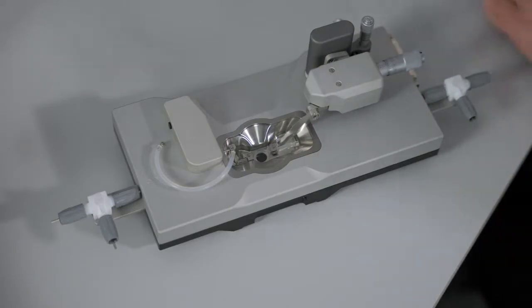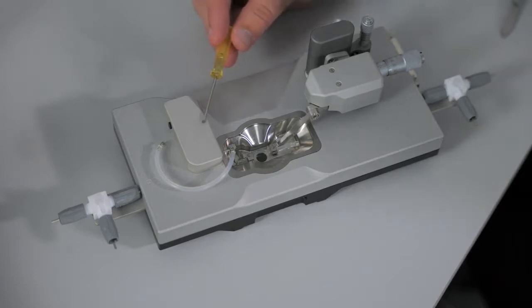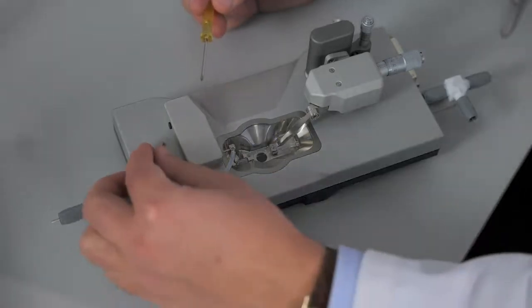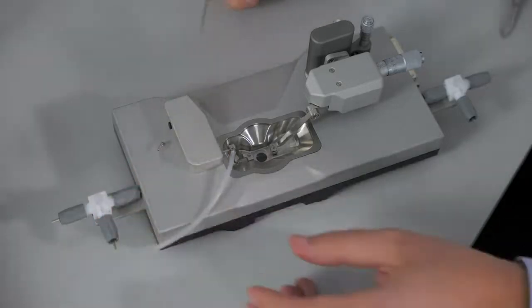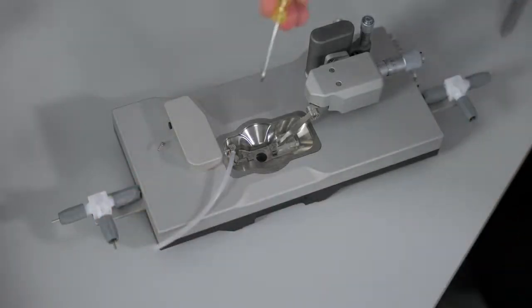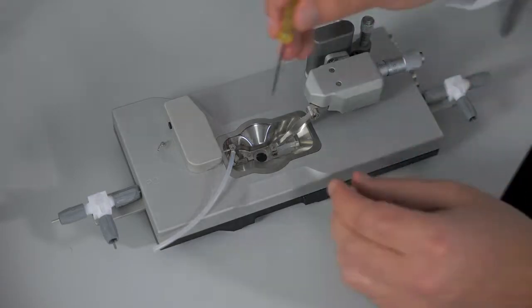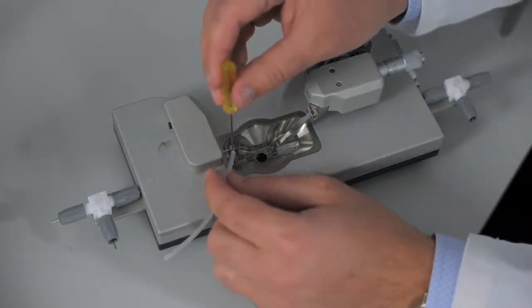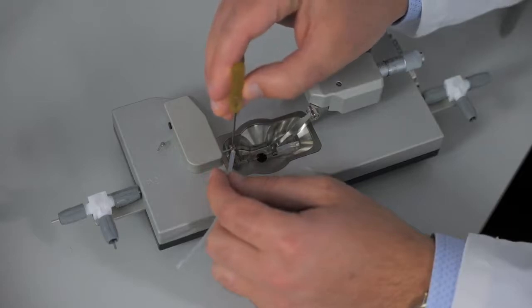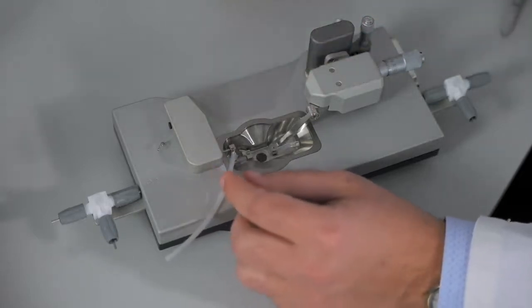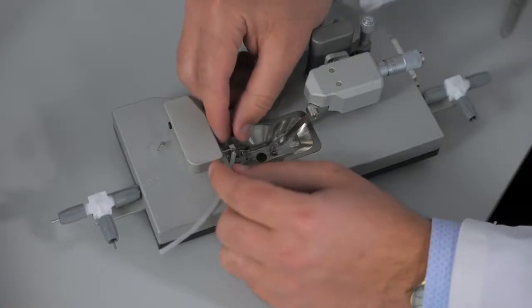If you need to replace the left side cannula, remember that this is attached to your force transducer and you need to be very cautious whenever you are adjusting anything on the left side. First, you will remove the tubing from this port. Then you will loosen the screw on top of the transducer arm. Again, try not to push very hard, just use as much force as necessary. You can then slide off this mount.